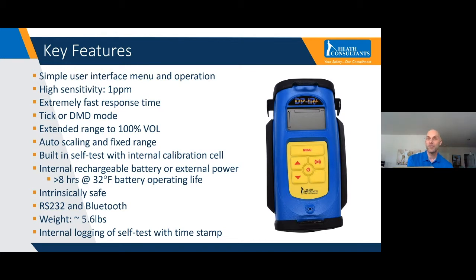It's intrinsically safe. So I mentioned it can be used as a combustible gas indicator. So being intrinsically safe means that you could also take the DPIR inside of a house in case you had gas that you needed to get in there. In case you were questioning whether there was gas inside the house, you can use it for that because it is intrinsically safe. Communication, downloading information can be done either via the RS-232 port on the back or Bluetooth. One of the other improvements with the DPIR Plus is the Bluetooth. We've improved that, and I'll get a couple slides that'll go into that here in a little bit.